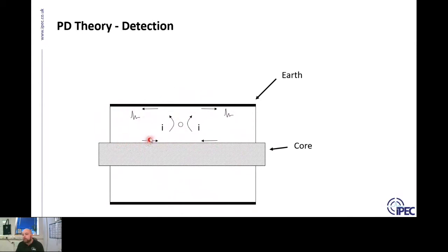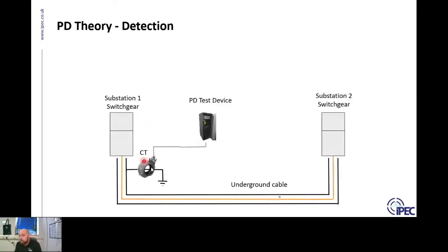Because those signals are opposite, we need to find a point along the cable circuit where we can separate the core and the earth — only at such a point do we have a chance of detecting PD activity. In this example, I've got the HFCT connected to the earth sheath back at the main substation on a medium voltage circuit — the most common place to attach an HFCT quickly. The PD signal travels along the inside of the earth sheath and out through the HFCT.